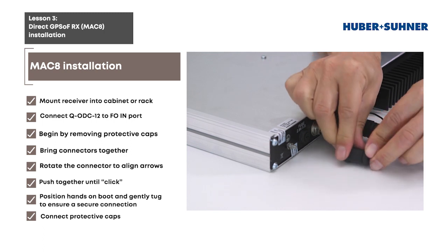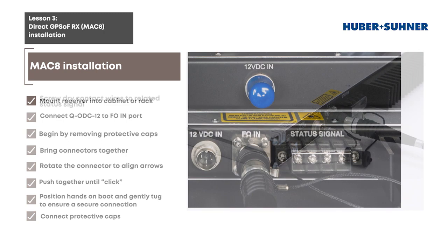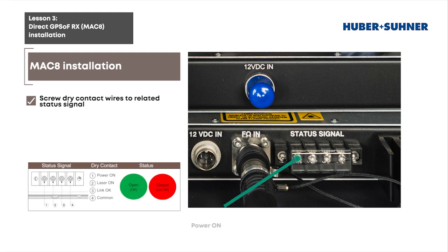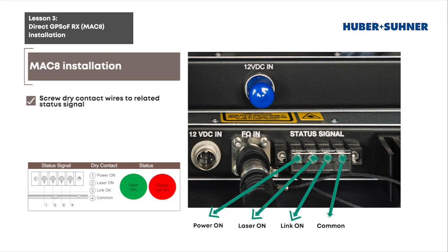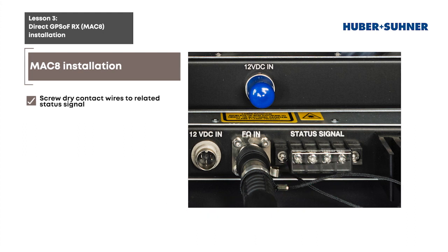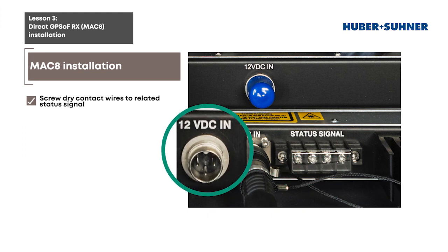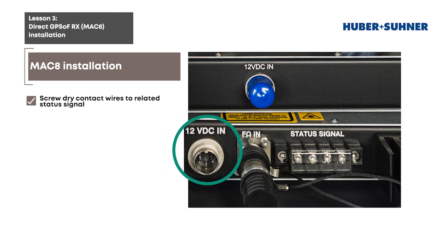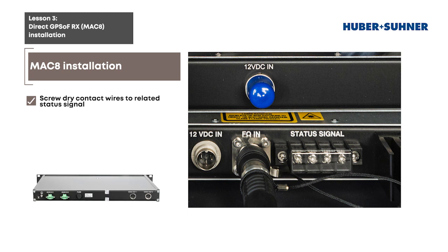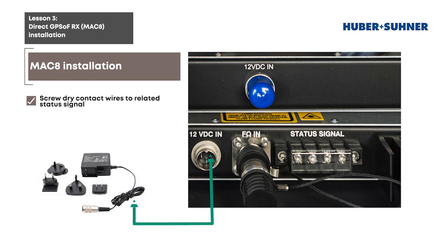When finished mating the QODC12 connector to the receiver, screw dry contact wires to the related status signal contact on the back of the module. Make sure you wire the appropriate port to the appropriate dry contact. Connect the power connector to the 12-volt DC 1.6 amp input port at the rear of the unit. Connect the other end of the power cable to the DC-DC converter 12-volt DC output 1 connection. You can also use the power outlet with supplied adapter.